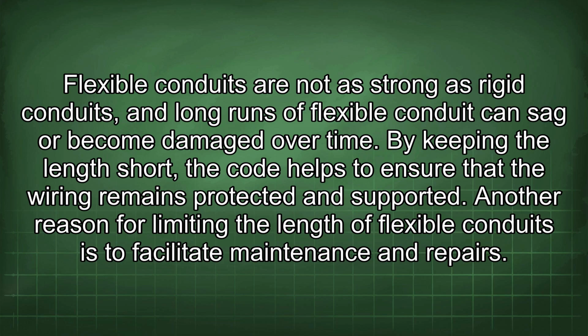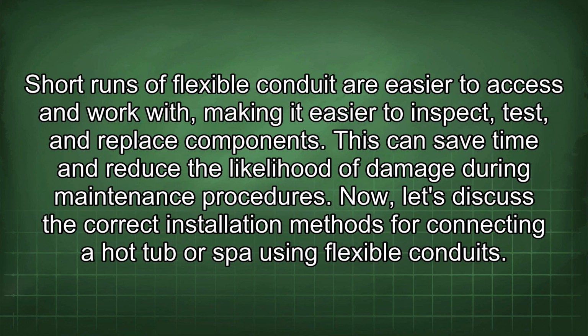Another reason for limiting the length of flexible conduits is to facilitate maintenance and repairs. Short runs of flexible conduit are easier to access and work with, making it easier to inspect, test, and replace components. This can save time and reduce the likelihood of damage during maintenance procedures. Now let's discuss the correct installation methods for connecting a hot tub or spa using flexible conduits.